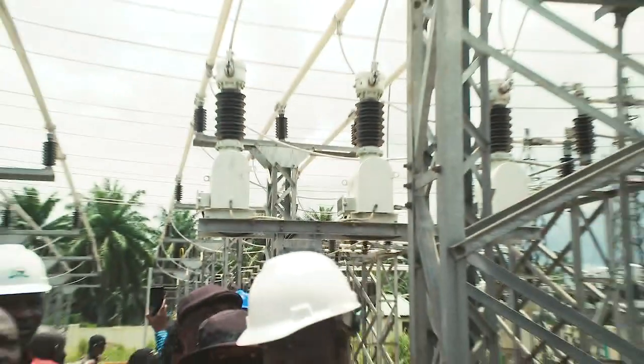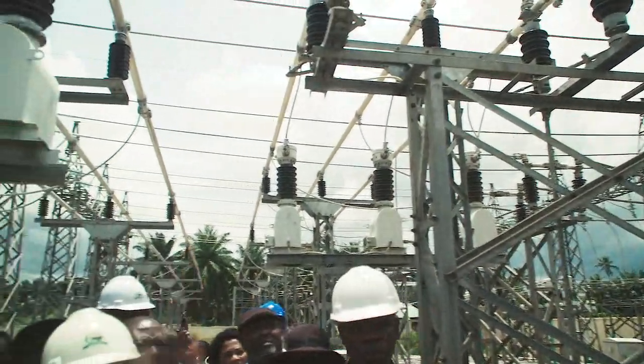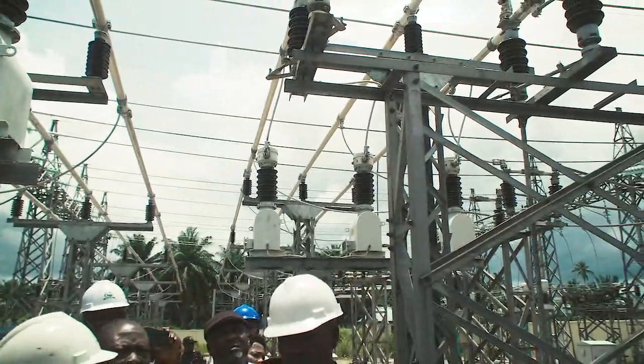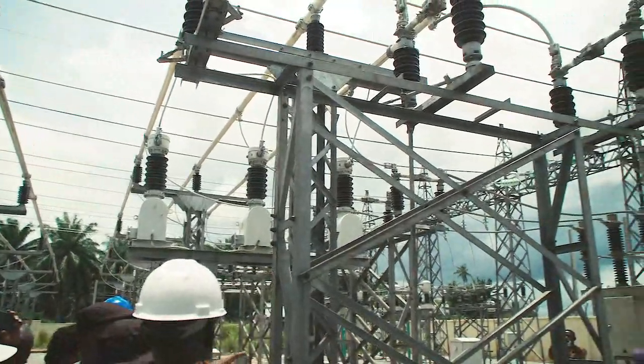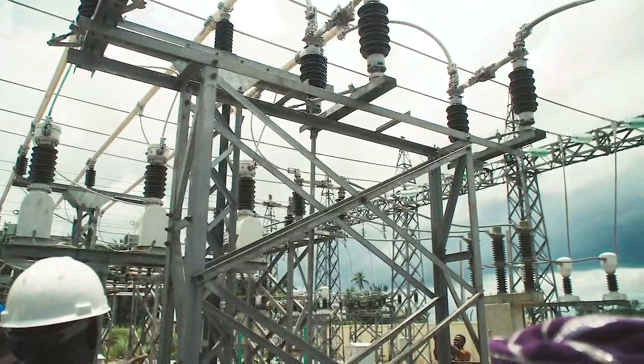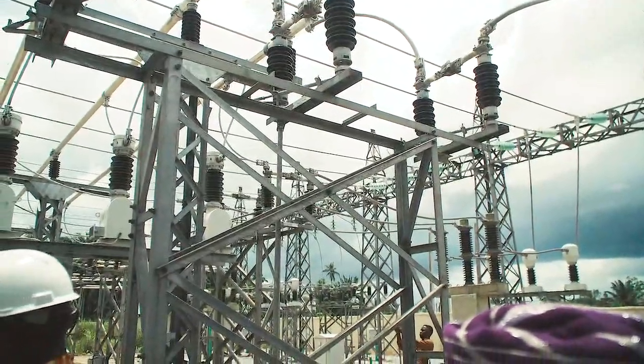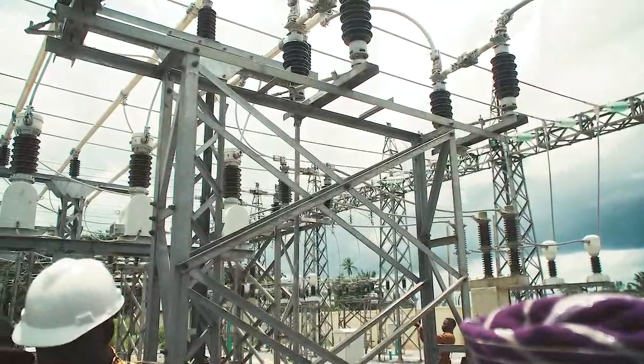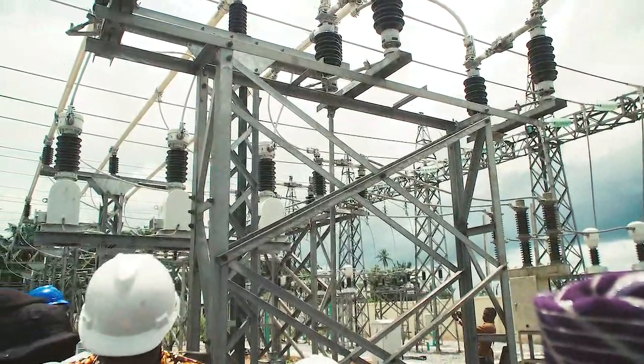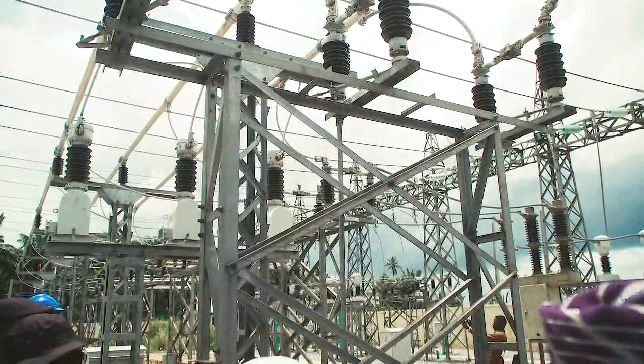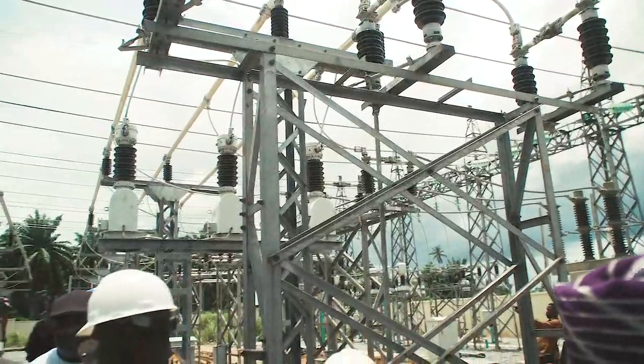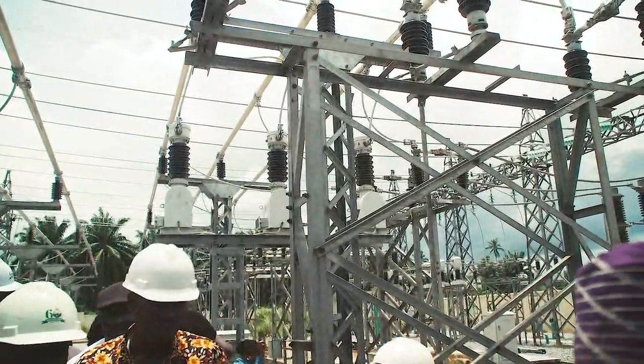The feeders, as can be seen, you have 3 of them on each side. In between them, you have the coupler. That is the breaker coupler. And you usually have what we call the reserve bus bar breaker. In which case, if there's any fault on any of the 33 kV feeders, you bring this breaker in. So you have no downtime. That is the beauty of this substation.